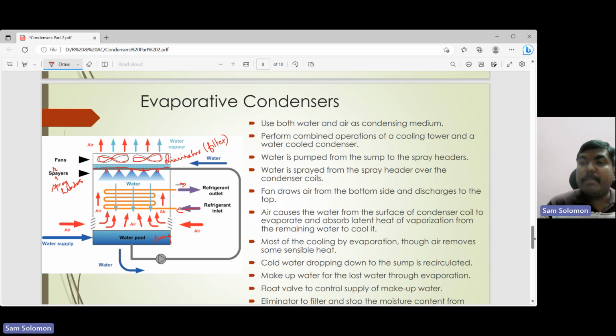Because we pump this water to the spray headers and the water gets evaporated as it falls down, there may be some loss of water due to the evaporation effect. For that, you can have makeup water. Makeup water can be added, and for this people use floating devices. Floats are used in order to control the supply of the makeup water. Okay, so that is how these evaporative condensers work.